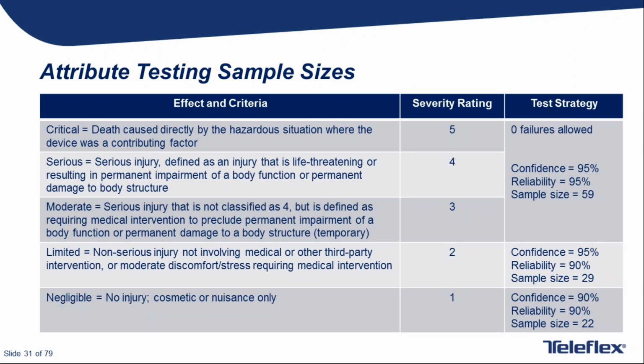Severity ratings of 3, 4, and 5 all deal with serious injuries, so the highest level of confidence and reliability, 95-95, is applied. There's also a distinction between severity ratings of 2 and 1 in terms of higher confidence being required for severity level 2. Because severity level 2 is still an injury, although non-serious, where severity level 1 is just a negligible cosmetic type of defect. So why should 95/95 be the highest level of design verification?